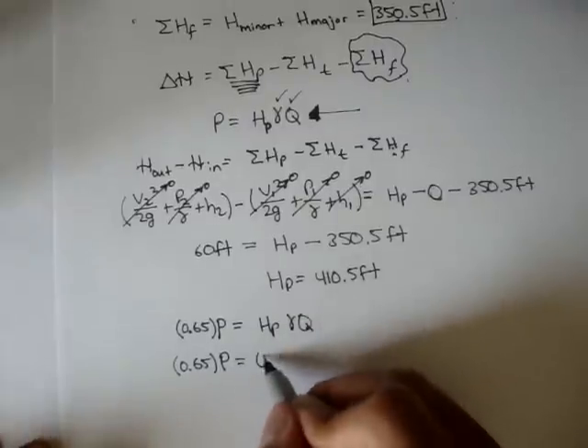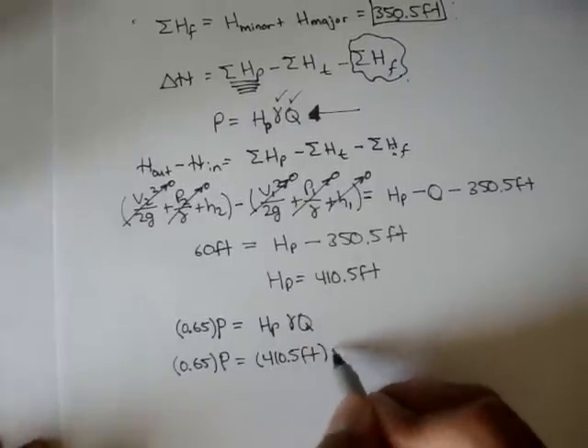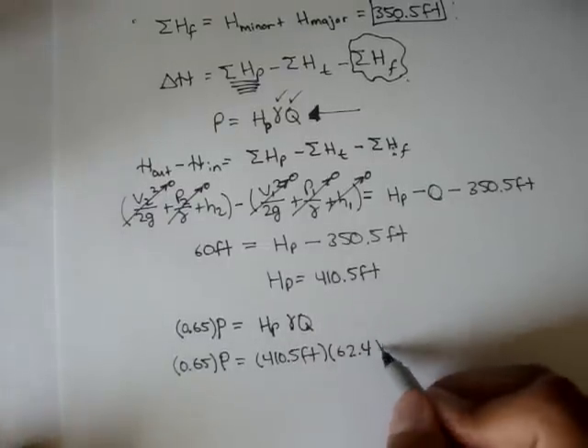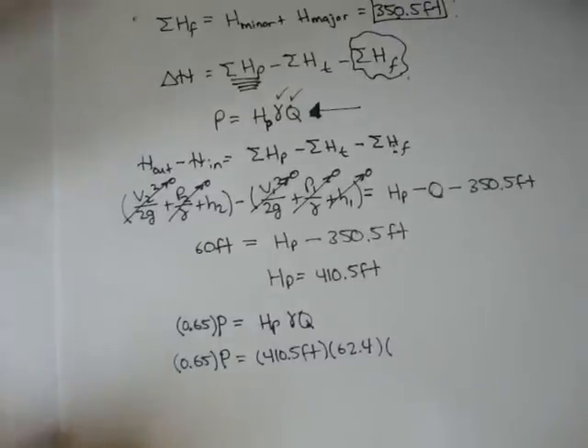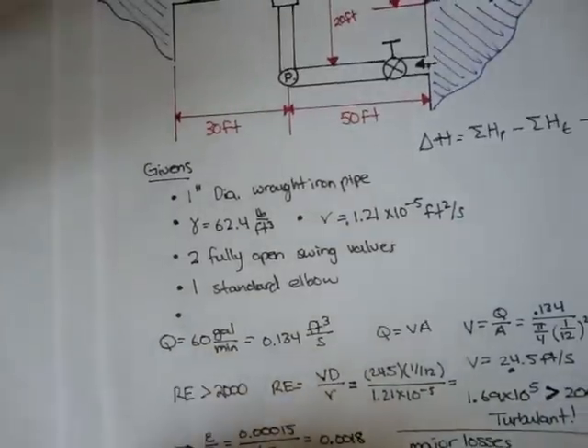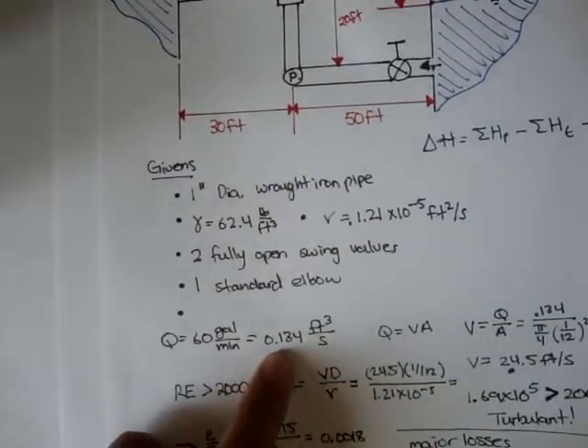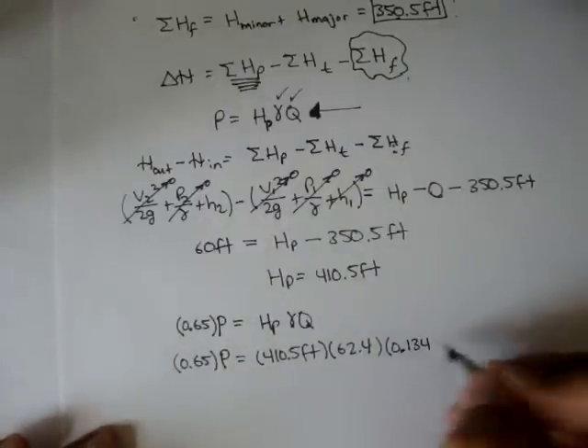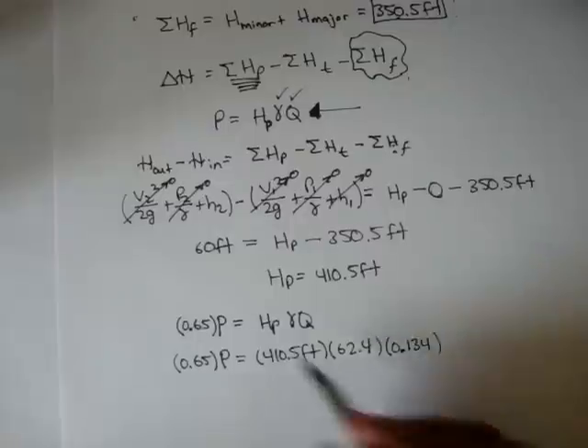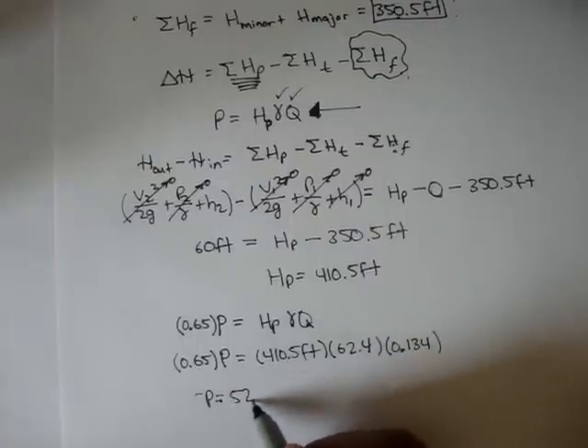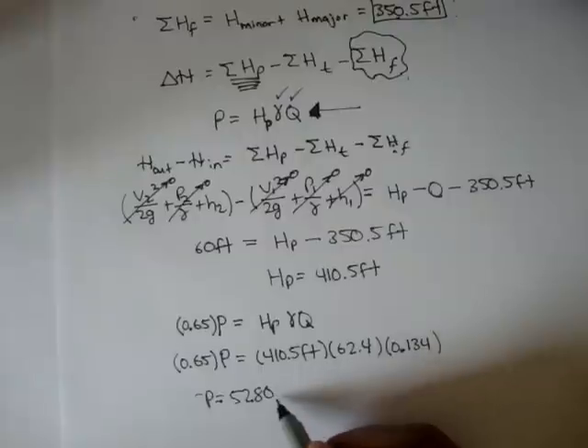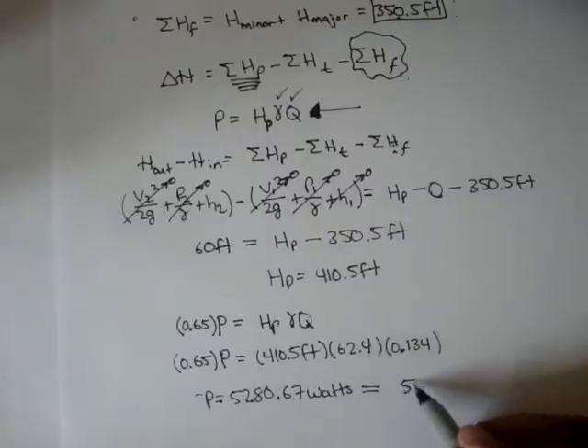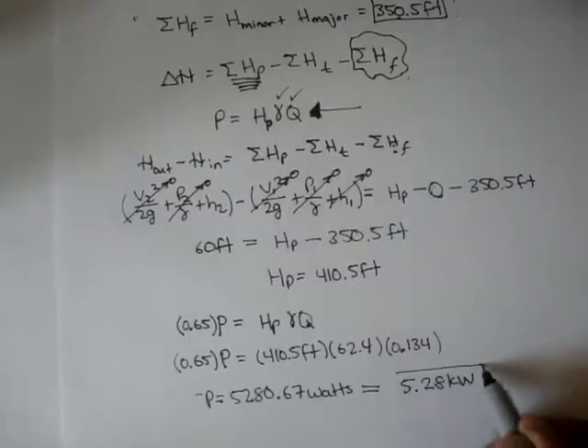And we can rewrite this a little bit more. Head pump is 410.5 feet, times the specific weight of the fluid, which is 62.4. And the volumetric flow rate, remember, in our first video, we found to be Q is 0.134 feet cubed per second. So 0.134. And if we solve the power, we get power is equal to 5,280.67 watts or 5.28 kilowatts.